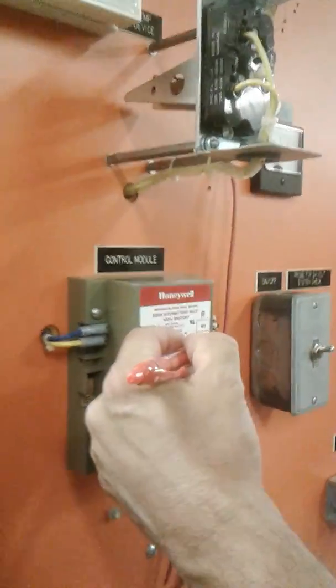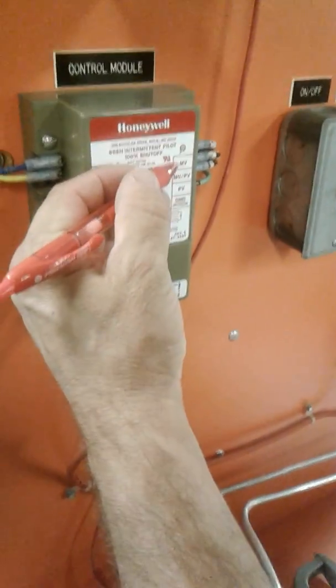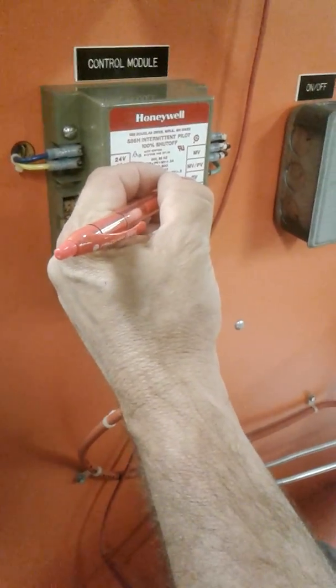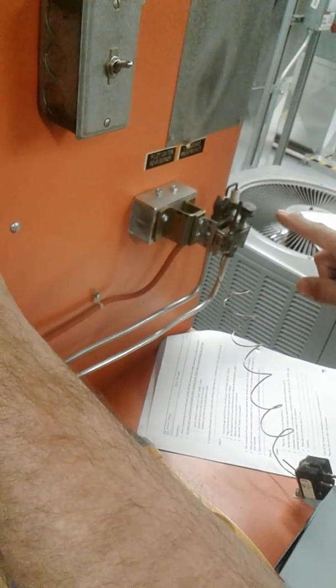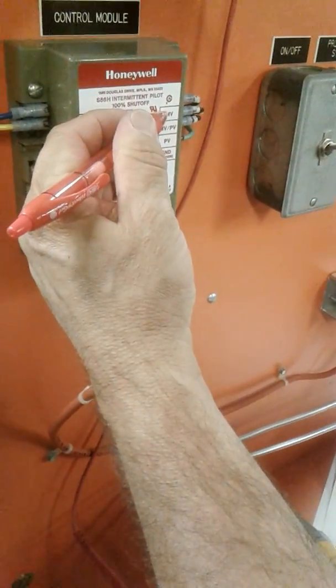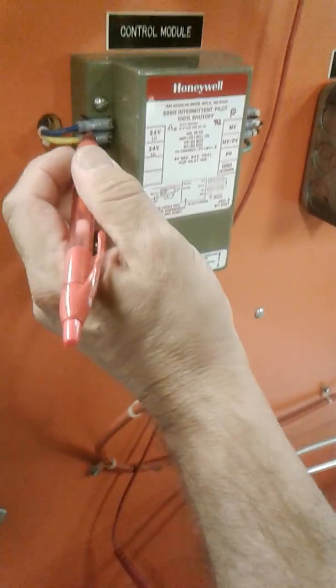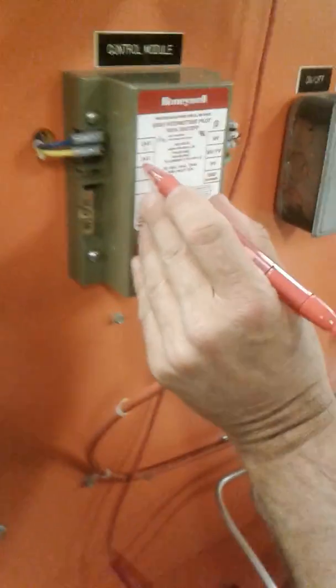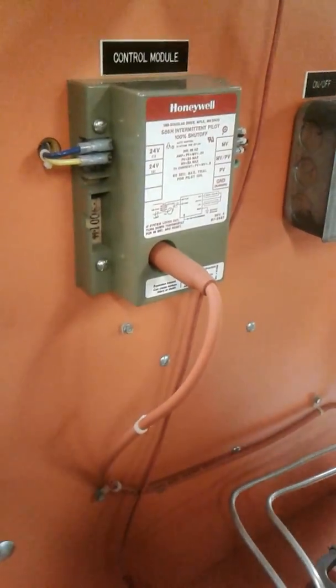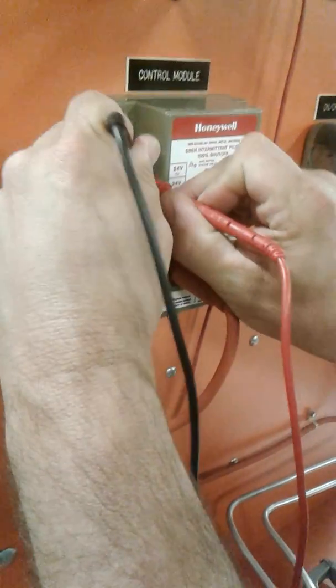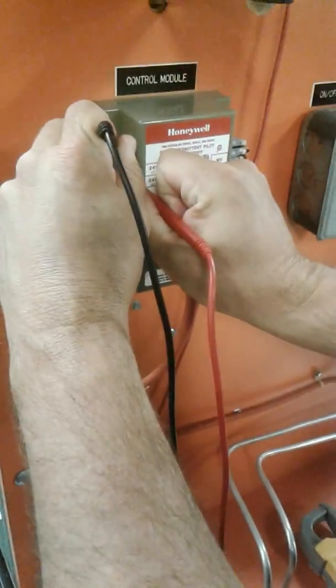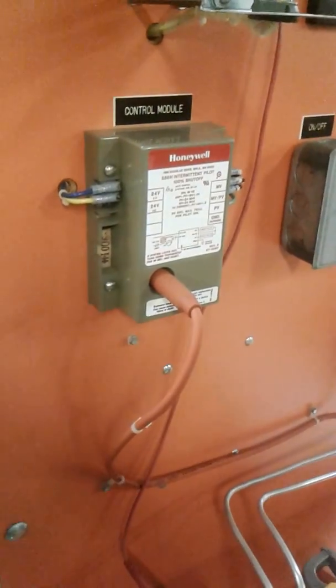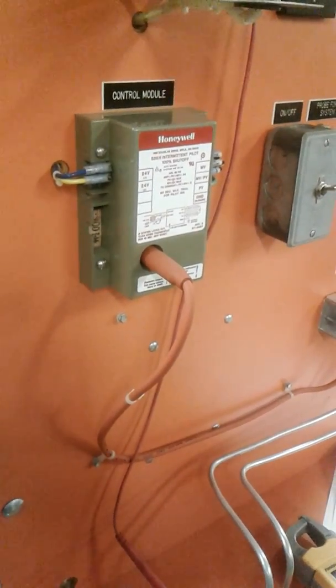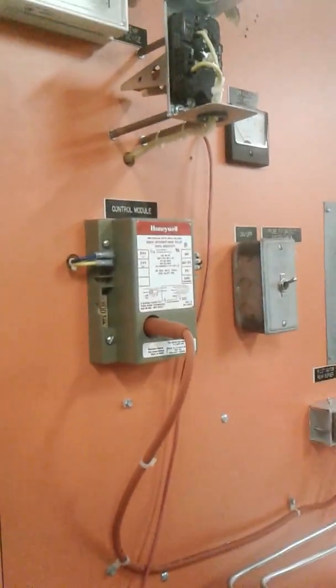Keep in mind the MVPV is common to PV. MVPV is also common to the main valve. Once our pilot lights, then it's going to light our main valve. So if we've got no power coming in, because he said the transformer's bad, and he's right because I put my meter there, let's check it out. Let's verify it again. I've got no power coming in. So I've got no 24 volts being controlled to it. So number 1 controls the transformer. So we have a bad transformer because it's not supplying control voltage to our module.